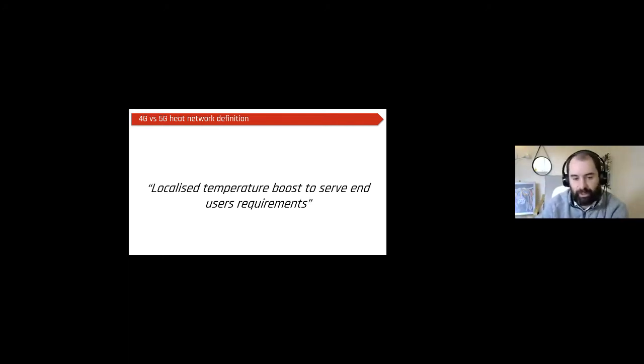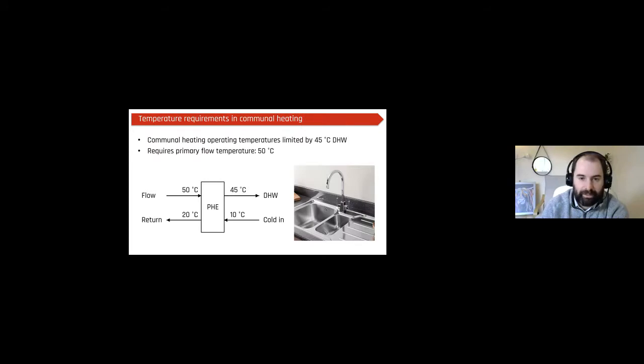5th generation is where you need localized temperature boosting to serve end user requirements. In communal systems that means you're usually limited by the hot water temperature. You can get space heating systems, underfloor heating systems, down to low temperatures, but you'll always be limited by an absolute minimum of about 45 degrees for domestic hot water.